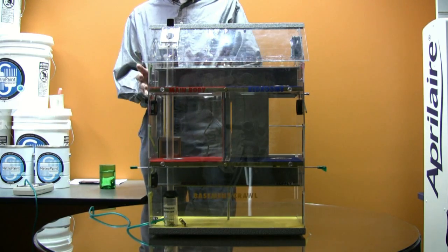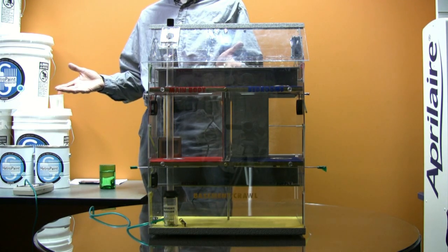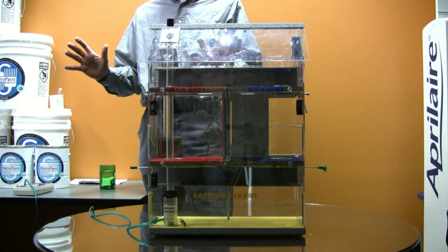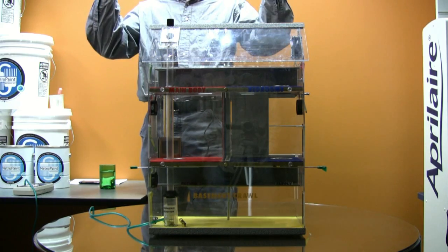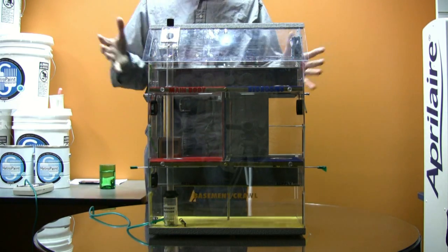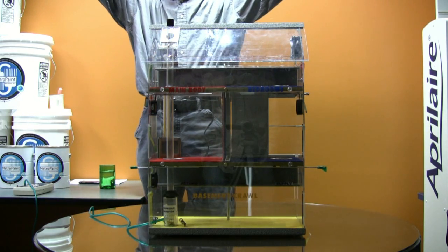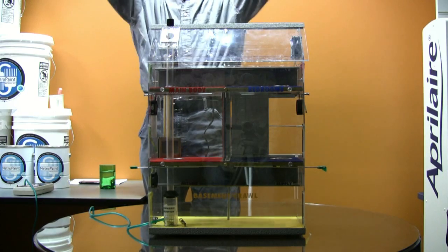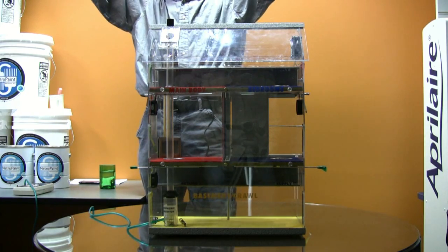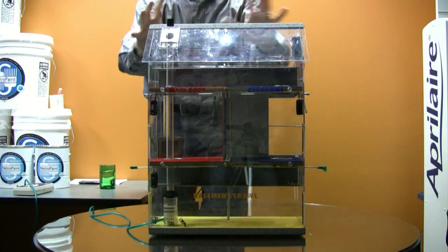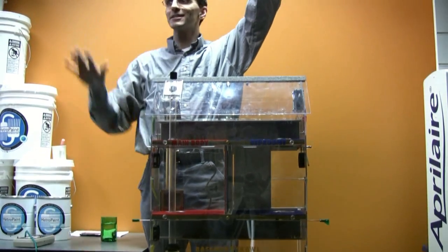If this were the typical house, and you're thinking about how the stack effect works in the house, you've been learning about the stack effect in class, right? A little bit so far? No. Stack effect is the concept that hot air rises. So within any given building, hot air is always trying to leave out the top of the building. Because of that, as it tries to get through the ceiling, it builds up a positive pressure up there. And because within a container, like a building, if one part is positive, somewhere else it has to be negative.